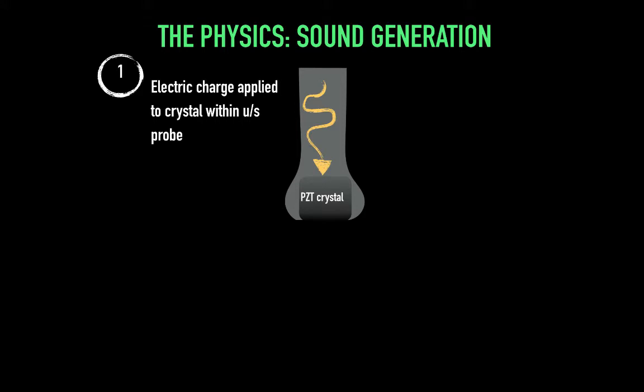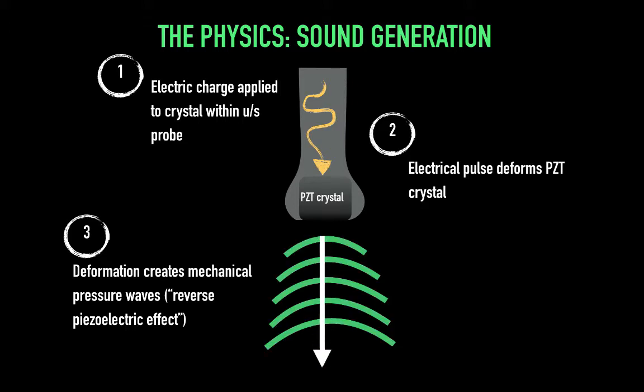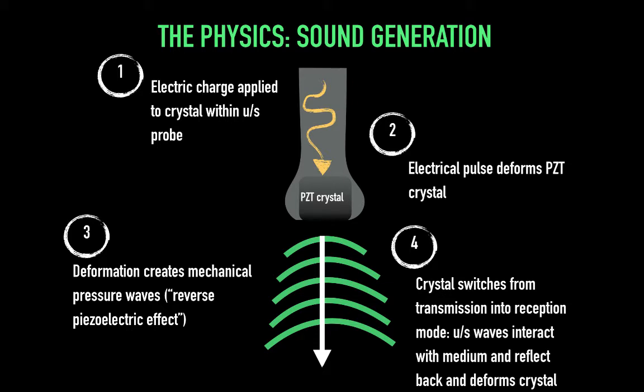Here we'll cover sound generation. An alternating electric current in the head of the probe affects piezoelectric material or crystal in the probe head. The mechanical properties of crystals determine the range of sound wave frequencies produced. When electric charge is applied to the crystal, the material expands and contracts, generating mechanical strain — leading to mechanical pressure waves in what's called the reverse piezoelectric effect. To receive the signal, the crystal switches from transmission into reception mode. Ultrasound waves interact with the medium and tissue boundaries, reflect back, causing crystal deformation and generation of electrical current — the direct piezoelectric effect. This cycling repeats several thousands of times per second, creating a real-time image.